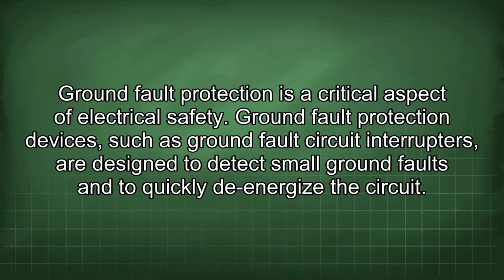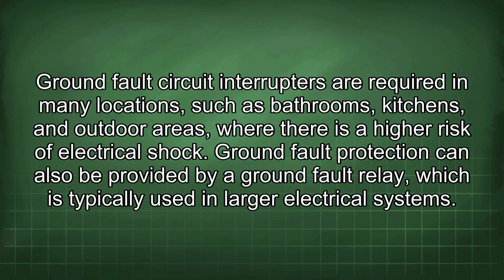Ground fault protection is a critical aspect of electrical safety. Ground fault protection devices, such as ground fault circuit interrupters, are designed to detect small ground faults and to quickly de-energize the circuit. Ground fault circuit interrupters are required in many locations, such as bathrooms, kitchens, and outdoor areas, where there is a high risk of electrical shock.